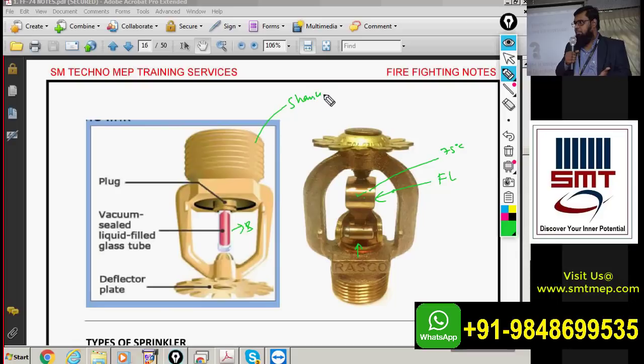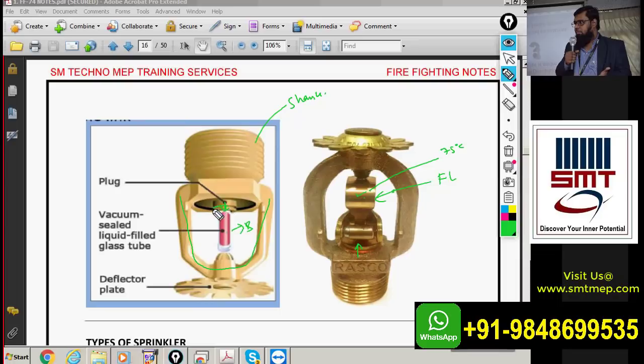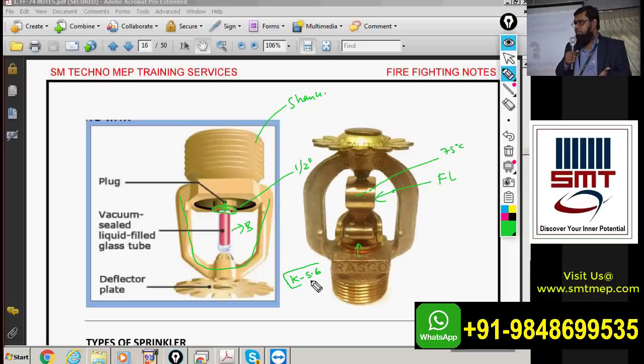The threaded portion of the sprinkler is called the shank, and the outer structure is the frame. Here is the bulb — a mechanical thermal sensor. Water starts flowing from the opening, called the orifice, when the bulb breaks. The standard orifice diameter is half inch; we also have 3/4 inch, 1 inch, and other sizes. The standard half inch corresponds to a K-factor of 5.6.